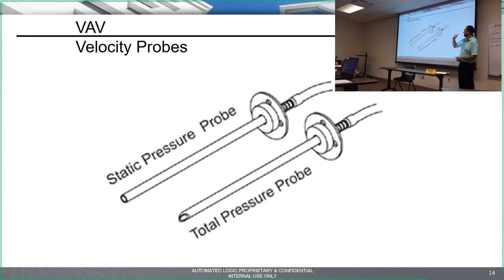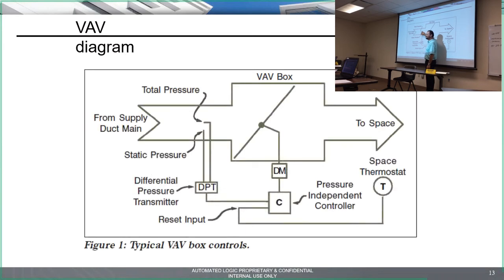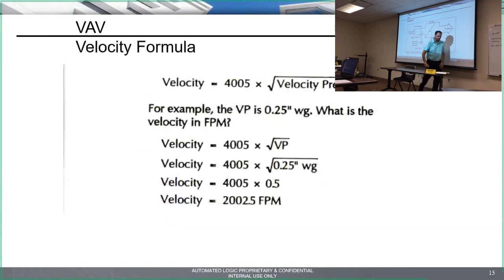So jump back to that slide. If I subtract this pressure from this pressure, the pressure difference is just the pressure running down the duct. Does that make sense? You guys follow me? You can stop me at any time and say, hey, you're not making sense. But the static pressure, if you subtract static from the total, it gives you velocity pressure. It's actually the velocity of the air running down the duct, right? Okay. So go ahead and jump to the next one.